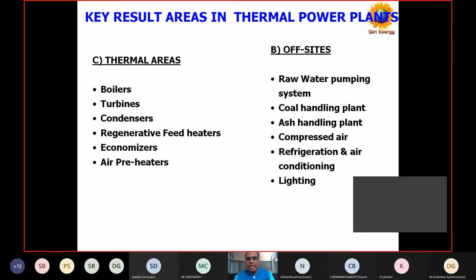Of course we are doing mostly energy analysis and performance analysis of each and every equipment to evaluate their efficiencies and find out where the margins are available when compared to design, and give our recommendations with cost benefit analysis. So suppose there is an efficiency improvement of the boiler, there is a margin of 2 to 3%. There may be a problem with the mill, there may be a problem with the firing, there will sometimes be problems with the burners. Even from the insulation side, there may be a lot of heat losses, radiation losses. Those things we will try, and maybe the major loss we encounter is the excess air. If you're able to monitor and control the excess air, that is a major benefit.